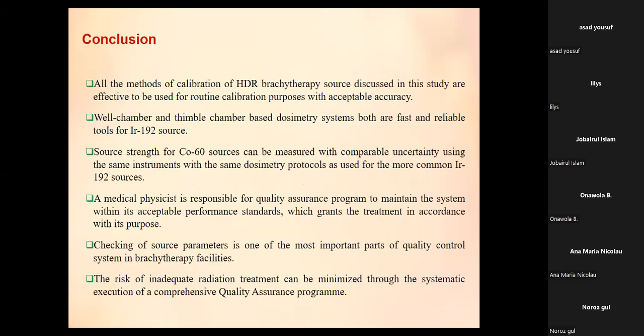So now I conclude my lecture. In conclusion, the methods of calibration of HDR brachytherapy sources discussed in the study are effective to be used for routine calibration purposes with acceptable accuracy. Well chamber and Farmer chamber based dosimetry systems are both fast and reliable tools for iridium 192 sources. Source strength for a cobalt 60 source can be measured with comparable uncertainty using the same instrument with the same dosimetry protocols as used for the more common iridium 192 source.